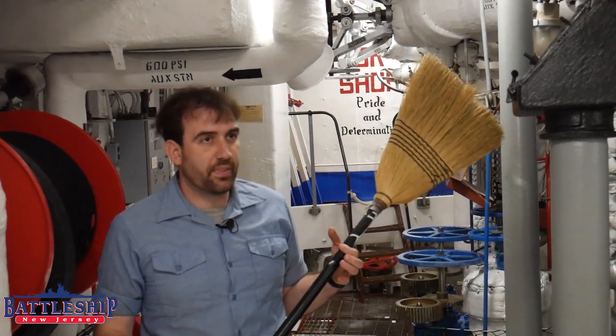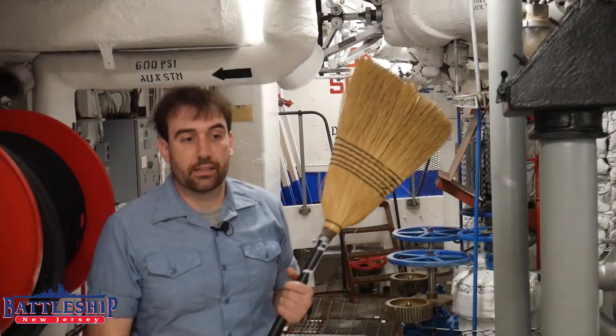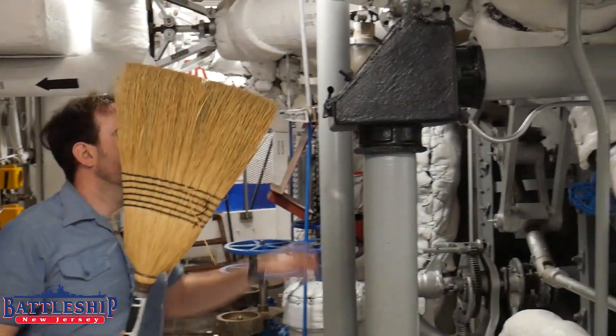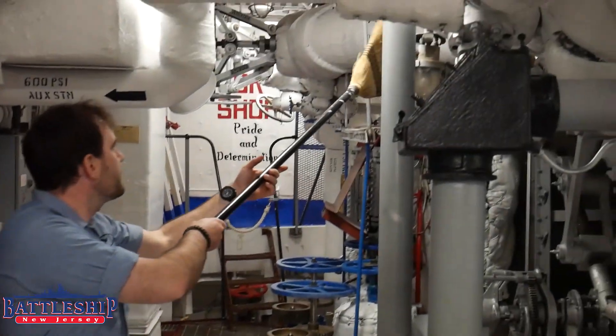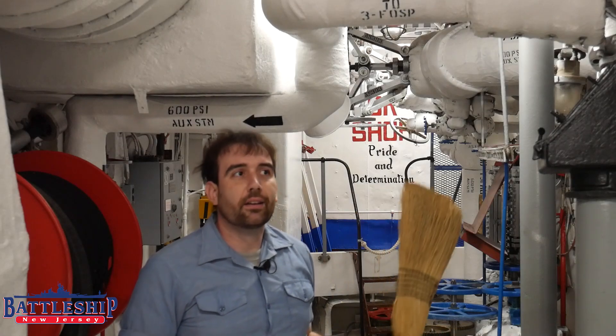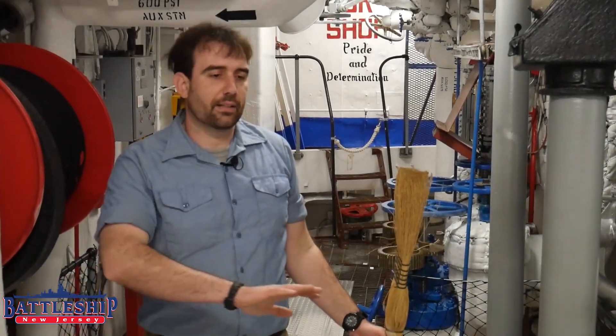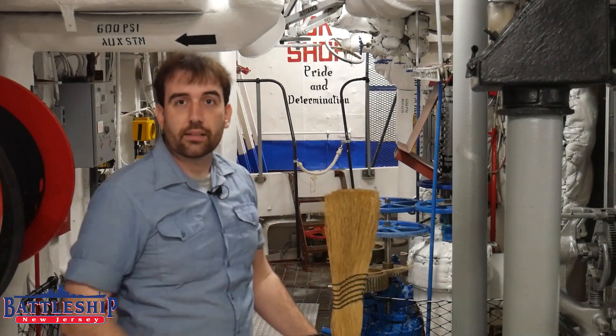So not just for the extremely rare and unlikely instance that you've got to literally sweep your pipes, but any sort of maintenance that needs to go down. It also helps you remember off the top of your head — oh, there's a valve right here, find the leak here, I can shut this valve, and now I've isolated it to the point that we can start doing maintenance work. And eventually we're going to find the trouble spot — it's going to cut the bristles right off the broom — and there it is. We've got to isolate the auxiliary steam line from boiler number three, so you shut that down. The ship does have eight boilers, so she can still run at a pretty decent speed with one shut down — these would often be shut down for maintenance, so it's no big deal. Wait for it to cool down, wait for the pressure to bleed off, and then you can start cutting at the insulation and find your leak.